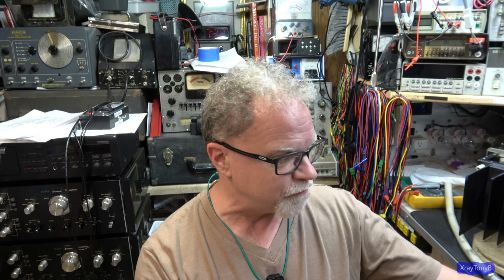So much so that neither one of us flinched. We just looked at one another, and he said, well, I guess we didn't get all the shorts out of it yet, did we? And I said, no. And I said, there is a very good example of when you have the wrong fuse. Because when that thing blew, it made that loud explosion, because once that filament vaporized inside that fuse cartridge, it turned to plasma, and it kept conducting until you had fire.